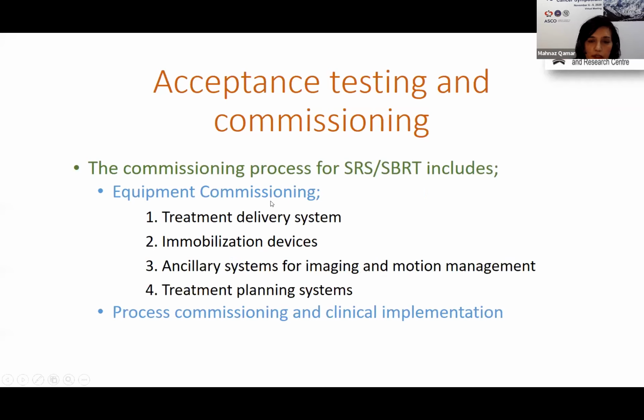So what is commissioning? Is it just for the machine or the Linac, or is it basically all the equipment that is going to be used in that process? Which includes the treatment delivery system, the immobilization devices, and ancillary systems for imaging and motion management. So any system that we're using for, let's say, MR, there has to be some kind of background QA checks for that also, to see if the images received from that system are going to be accurate enough, because all the tumor delineation is performed on those images.